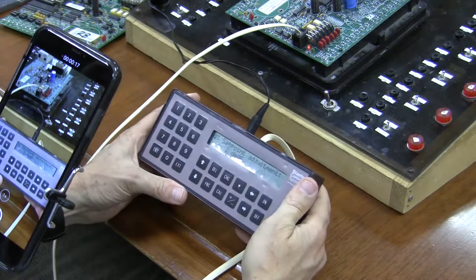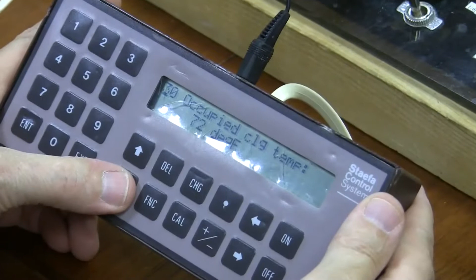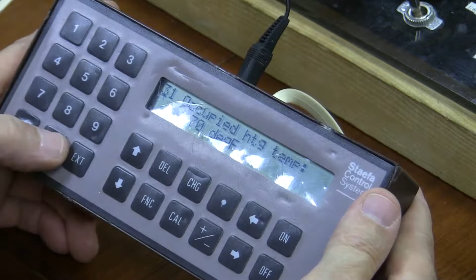That's my offset, right? Now if I hit EXT and I go out to the tens, I'm going to come to one here that says set points. So I could hit enter on set points and I can see, look at this. My occupied cooling temperature is 72 degrees. And so then I could go down and my occupied heating temperature is 70 degrees, but my set point adjust knob was at 2. So that means my heating's at 72 and my cooling's at 74. Right? And so now if I go back here to 0, I can say now my zone sensor, am I within that range? And that would probably be the very most basic thing that I would do, right?